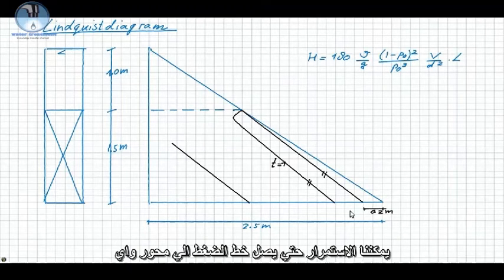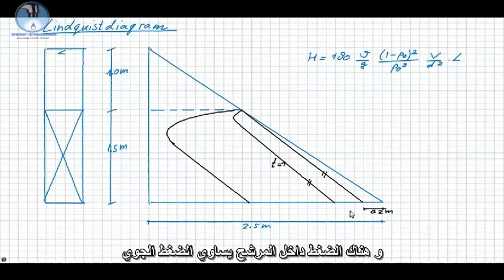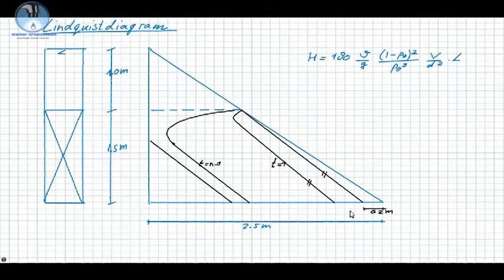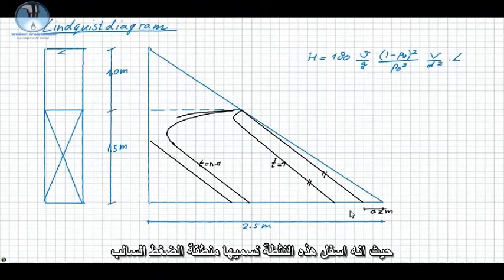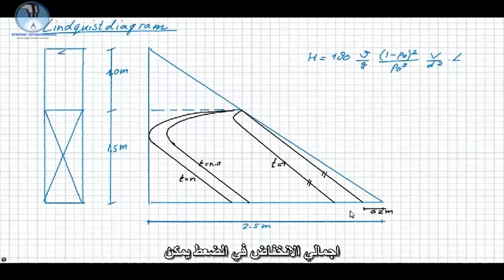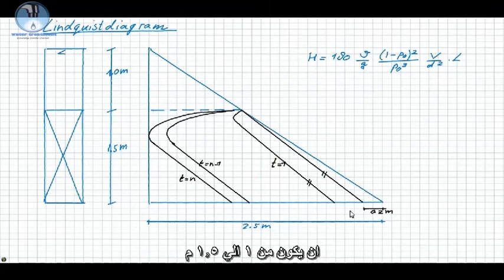Theoretically, we can continue until the pressure line touches the y-axis, where the pressure in the filter is equal to the atmospheric pressure. This point is critical because below this point — the zone of negative pressures — there is a risk of air coming out of solution, disturbing the filter bed. The total pressure drop can then be around 1 to 1.5 meter.